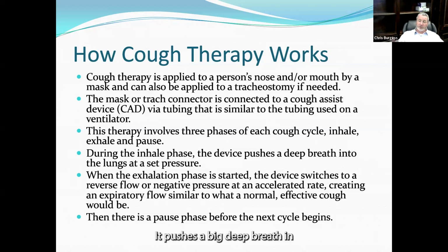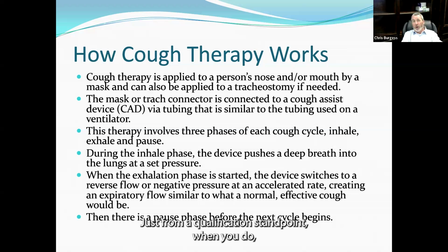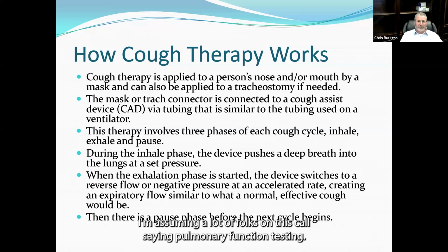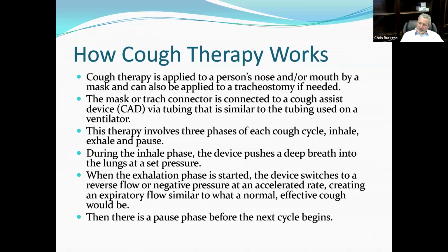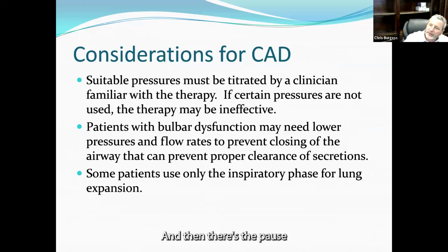So it's exactly that. It pushes a big deep breath in, you cough into it, it pulls pressure and airflow out. We're looking for a minimum airflow, just from a qualification standpoint. I'm assuming a lot of folks on this call have seen pulmonary function testing. When you do that forced vital capacity, if your exhaled flow doesn't hit 270 liters per minute, which is usually the insurance guideline, that's when we're doing cough assist, because that's what they determine to be an ineffective cough. And then there's the pause.